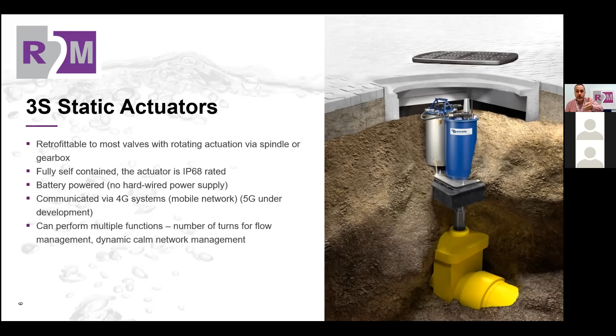The torque reading is important, because if a 12-inch valve needed 300 Newton meters to turn for its last operation, that valve's probably got something wrong with it. Valves are like us: if they sit still and don't move for a long time, they get stiff and ultimately jam. The torque reporting is useful because you can tell it that night to exercise itself 3 cycles, and by the third cycle the torque usually drops from 300 or 400 Newton meters down to 150, just from being cycled.